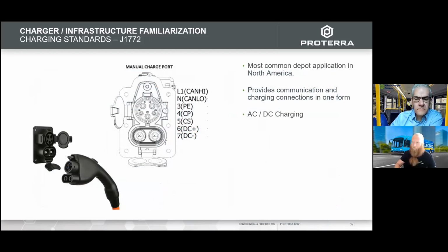For AC, you have level 1, which is 1.4 to 1.92 kilowatts, and level 2, which is 19.2 kilowatts. For DC charging, level 1 is rated at 80 kilowatts, and level 2 is rated for 400 kilowatts. But keep in mind that if it's rated for 400 kilowatts, there needs to be significant cooling, and the bus needs to be capable of receiving that amount. So typically, you're not going to come across a 400 kilowatt charger in practice, even though it's rated that high.